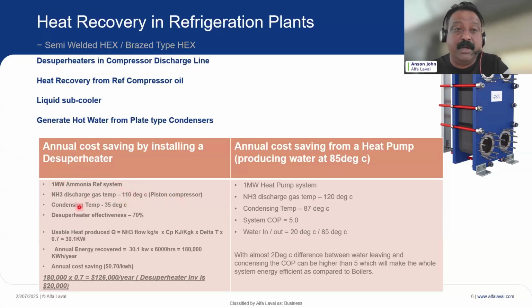And if you have a condensing temperature of 35 degrees C, and let's take de-superheater effectiveness as 70%, then based on a simple calculation, we all know this formula Q equals m Cp delta T, so around 30 kilowatts. And if this system is working for 6,000 hours in a year, we are talking about 180,000 kilowatt hours per year. And with 70 cents per kilowatt hour, we are talking about a saving of $126,000 in a year by installing a de-superheater.